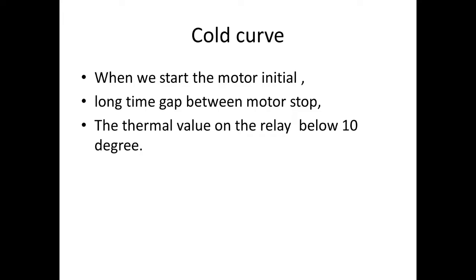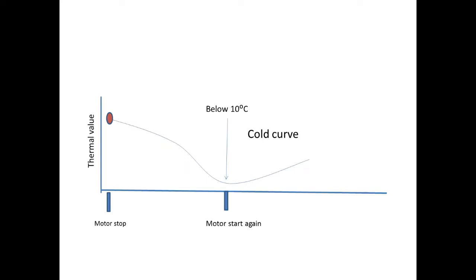In the same way, if you stop the motor for a longer gap — that means a 3 or 4 hour gap — and then start the motor, the relay curve will also follow the cold curve. This depends upon the cooling time of the motor. After you stop the motor, the thermal value in the relay will reduce slowly according to the cooling curve. When we start the motor again, if the temperature on the relay scaling is less than 10 degrees Celsius, then the relay is definitely going to use the cold thermal curve.